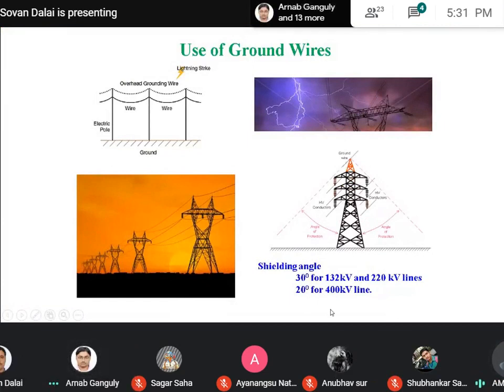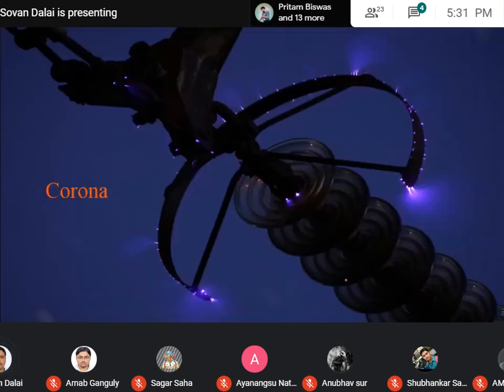Okay, so this is the shielding angle you have to provide if you want to protect your phase conductor from lightning strokes. This is the thumb rule we generally use. This is 30 degree for 132 kV and 220 kV lines, and generally 20 degree for 400 kV and above voltage levels. Okay. Now we want to discuss a little bit about corona. You are seeing this picture. It looks beautiful, but from the power utility point of view, it basically causes power loss. So we want to limit it so that no such phenomenon occurs.